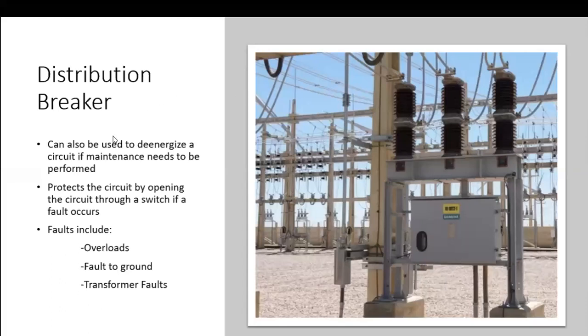A distribution breaker. Now we're getting ready to leave our substation and go out on our distribution lines, so we need some type of protection. A distribution breaker can be used to de-energize a circuit if maintenance needs to be performed, and it also protects the circuit by opening the circuit through a switch if a fault occurs. So if a power line falls to the ground or a tree falls on it or something like that, we don't want it to burn. We want it to trip out just like a breaker would in your home. So it protects against overloads, faults to ground, and transformer faults.